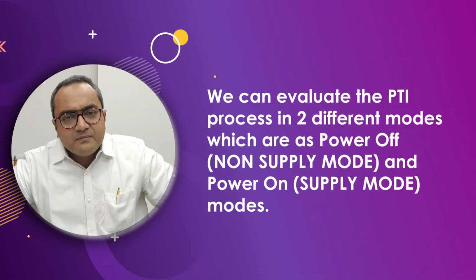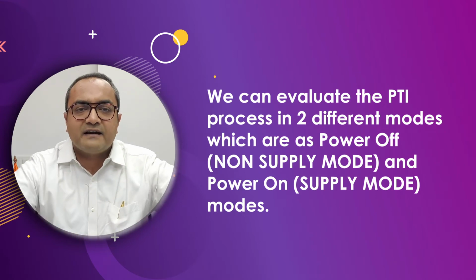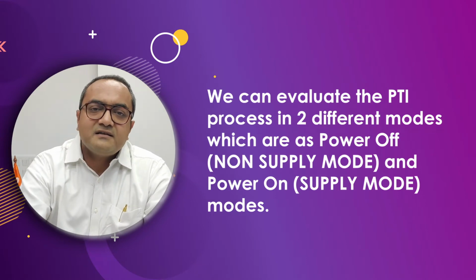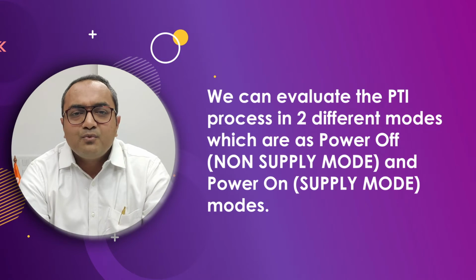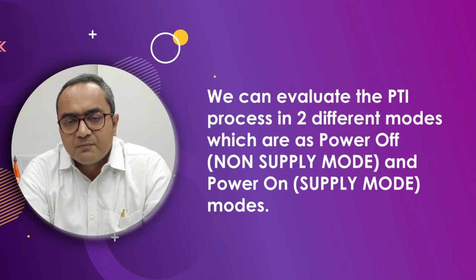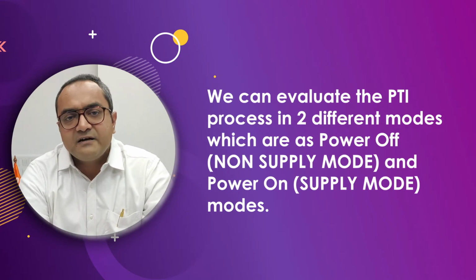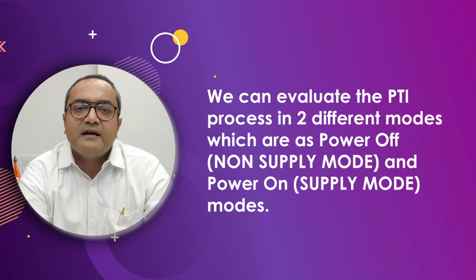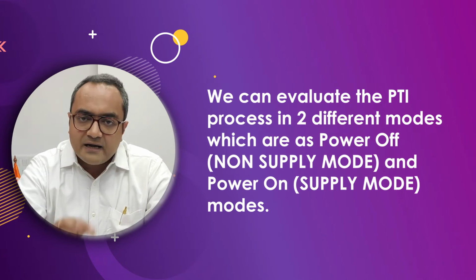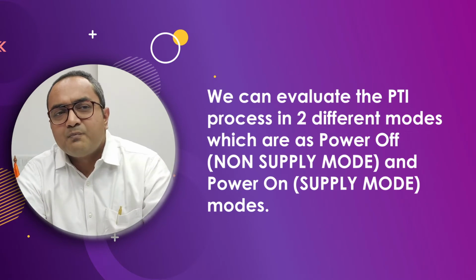So just to simplify, the PTI process can be evaluated in two different categories. One is the non-supply mode, and the other is the supply mode. Non-supply mode is basically power off, because as the container movement involves reefer equipment, when the reefer equipment is turned off, the evaluation can still be carried out. That is the non-supply mode. And with the plug-in and the equipment cooling function enabled, where the inspection happens, that is the power on mode. First we will understand the power off mode.